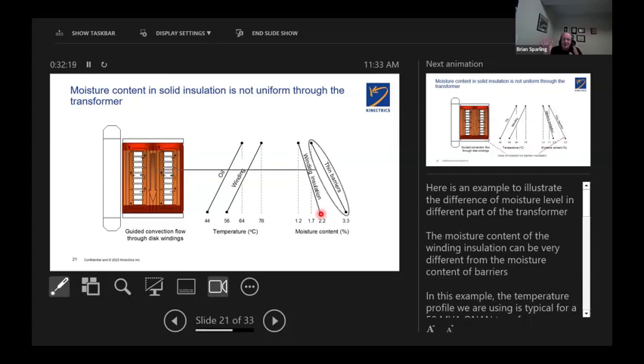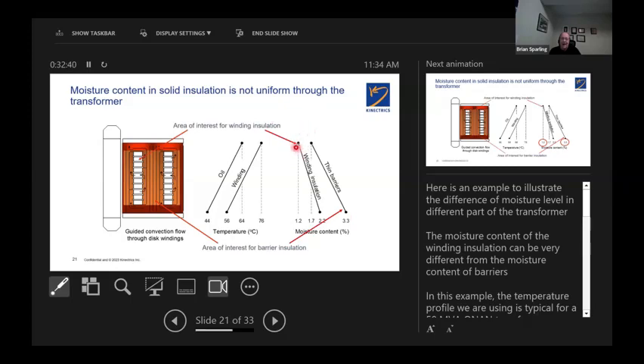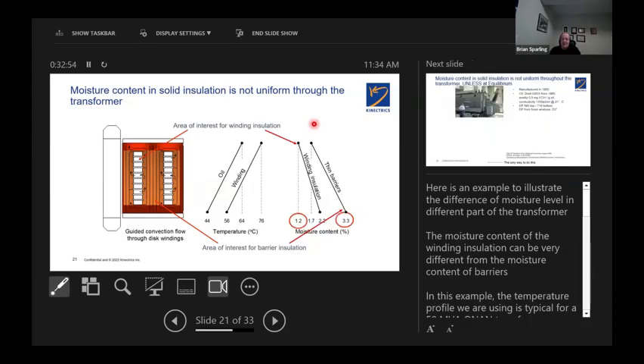And then you have the thin barriers. This is between the phases, between high and low voltage, so to speak, where you can have quite a difference. And so the area of interest from an online monitoring perspective is understanding how wet it is at the barrier insulation. That's where partial discharge can set itself up. And the area of interest at the hottest spot on the winding at the top, and understanding this from the bubble temperature evolution and from the aging point of view as well. Those are the two areas of interest, and we can get that with online monitoring. And you can see there can be a significant difference in moisture content in the paper, 1.2% in the paper at the top because it's hotter, and 3.3% because this is thicker material and it's cooler. So it's a difference.